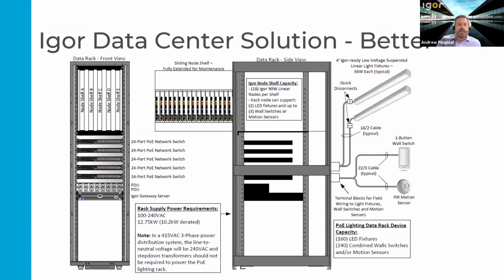And so we can encompass those in these vertically mounted shelves, which can slide out for maintenance purposes, but also allow good airflow and such to keep everything running nice and cool. And then below those in the rack, we have some typical cable management along with the actual PoE network switches. And so these are going to be IEEE 802.3bt switches rated for the 90-plus watts per port.